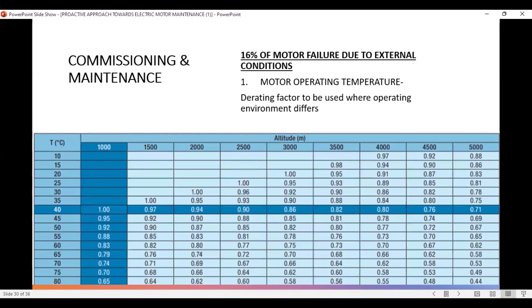Motor operating temperature is very critical. Motors are normally designed for an ambient temperature of 40 degrees Celsius. So if you have an ambient temperature of 40 degrees Celsius and you are going to operate it at an ambient temperature of say 45, there is a derating factor, and it's also designed for an altitude of 1,000 meters. So based on your application with a higher ambient temperature, you derate your motor to fit your application so that the motor will not fail prematurely.